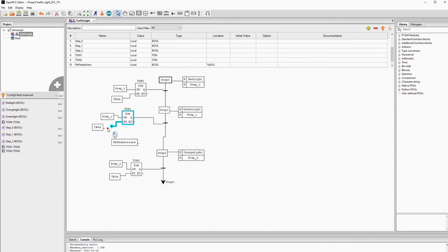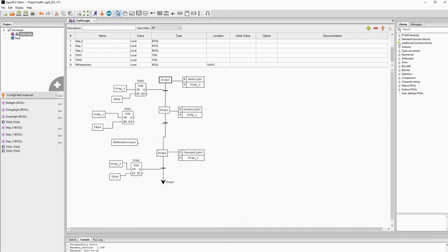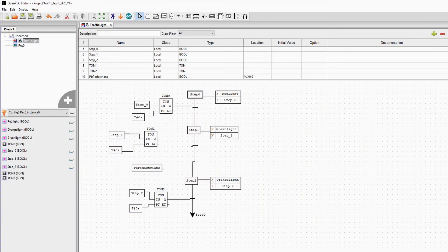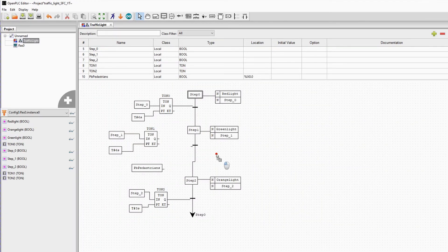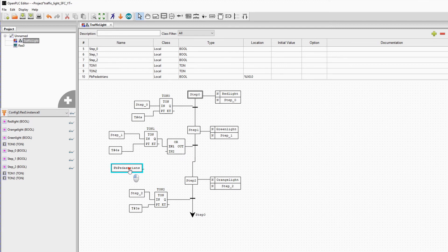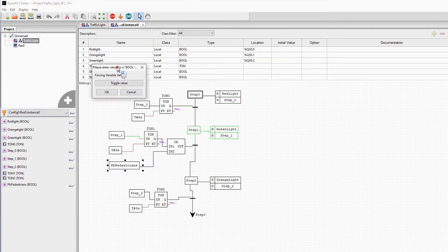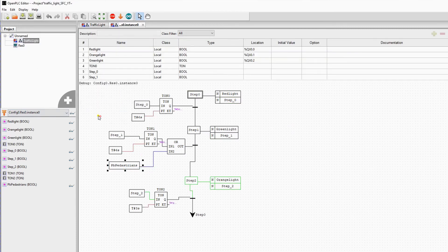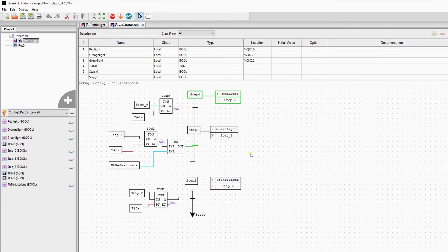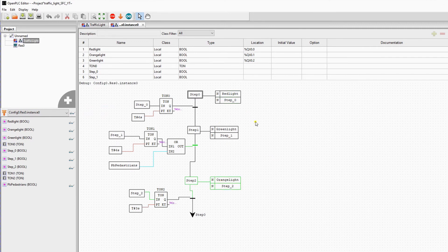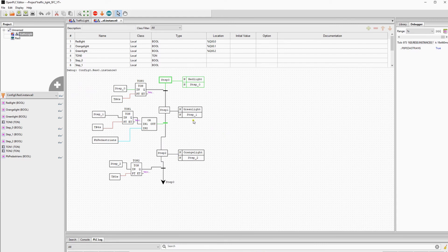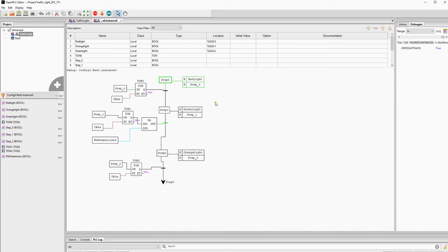You will use an OR gate to do this. Now we will simulate the code again and I will force the value of the push button. You now see the transition from step 1 to step 2 is always true. You can also see that if the push button would get stuck on the on state by either failing or vandalism, the green light would not be turned on.